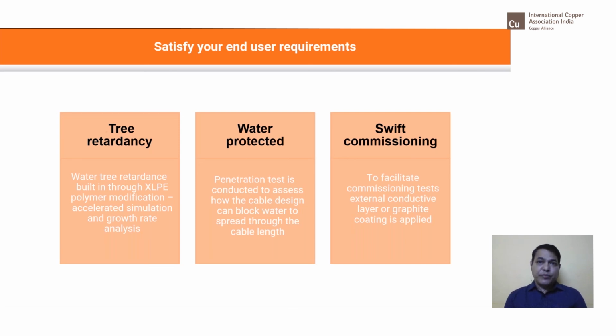A series of in-depth tests are undertaken as a part of the retardancy test. That is a big subject. To prove these characteristics, not only the cable compounds used, but the processing is also so important in a CCV line, the curing of the three layers. There is a simultaneous process, and also to confirm enhanced electrical performance, projected long life, high water tree retardance.